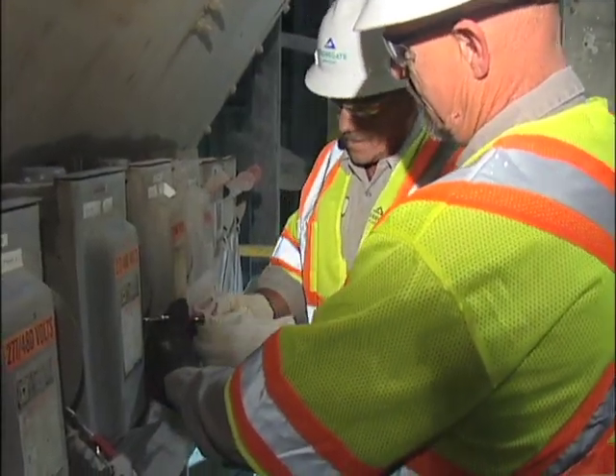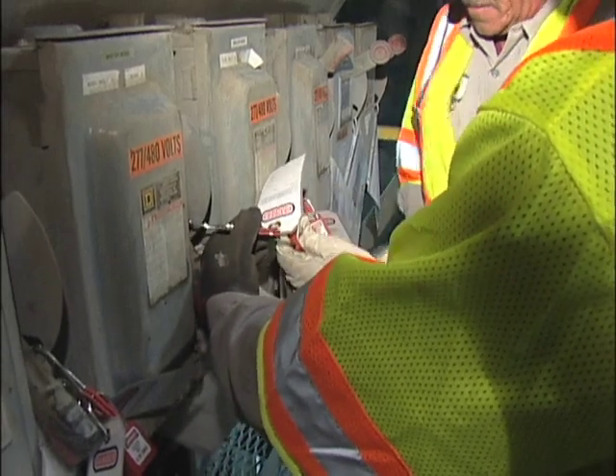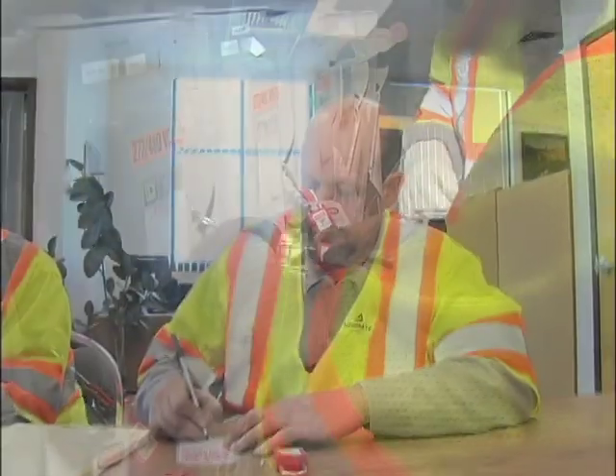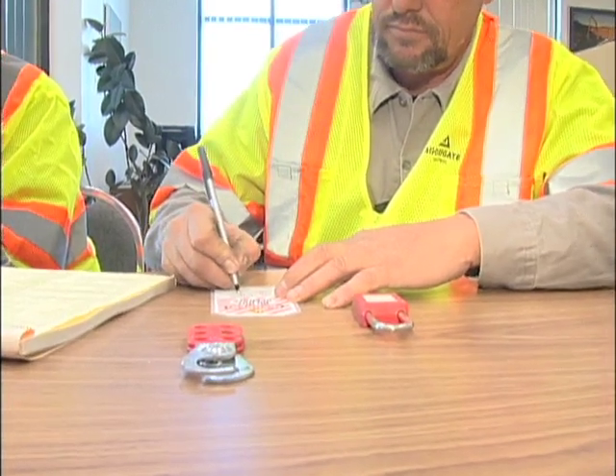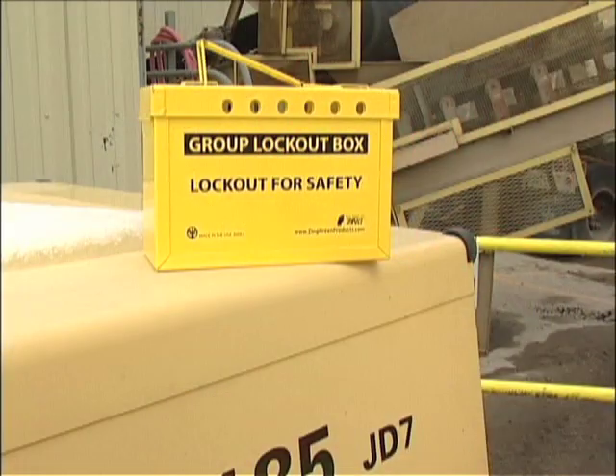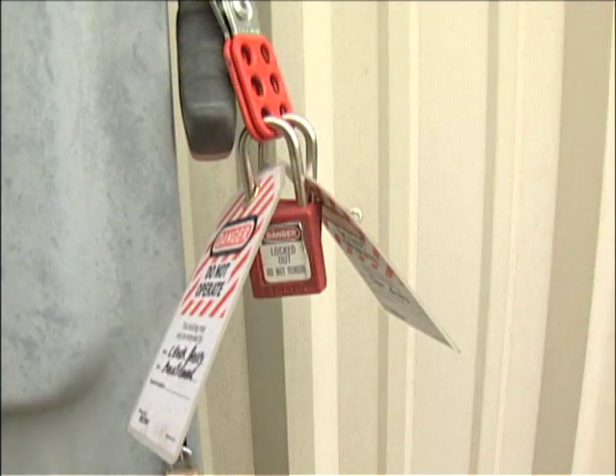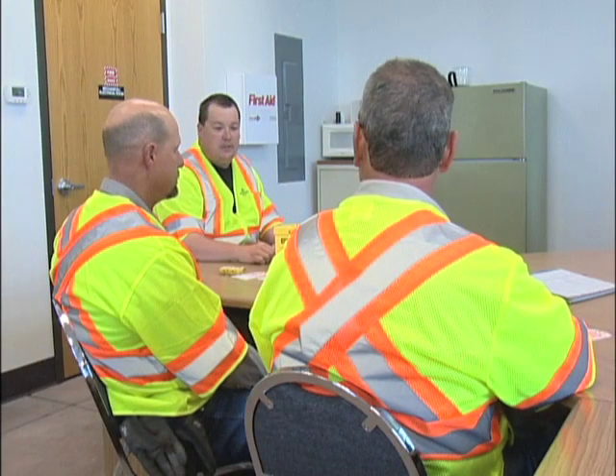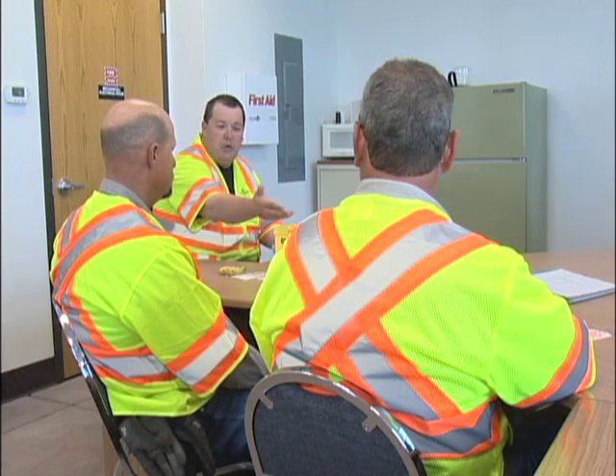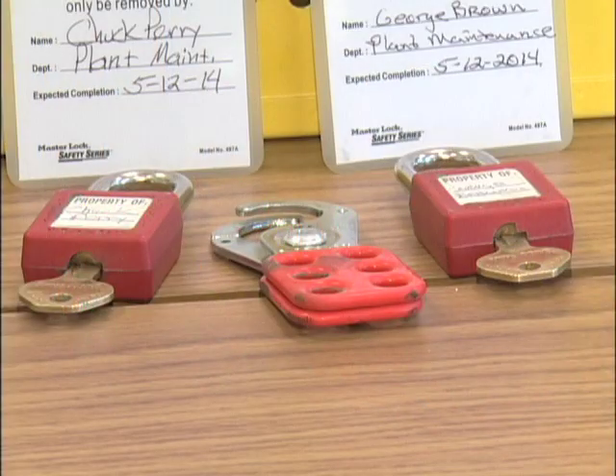Under lockout, tagout, and tryout procedures, all authorized employees must have tags and individually keyed locks assigned to them. As a best management practice, each of these employees is issued their own lock, and there is no sharing of locks and keys. A supervisor may keep a copy of individual keys as long as they are secured and not available for employee use. The one key per one lock eliminates the chances of someone bypassing a lockout, tagout, and tryout procedure. Lockout, tagout devices include hasps, covers, blocks, blinds, and the like.